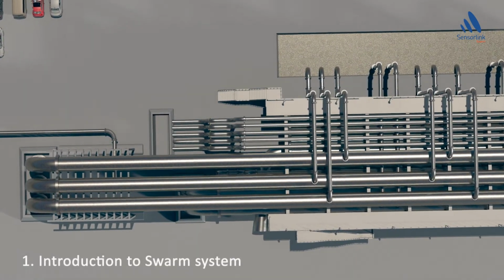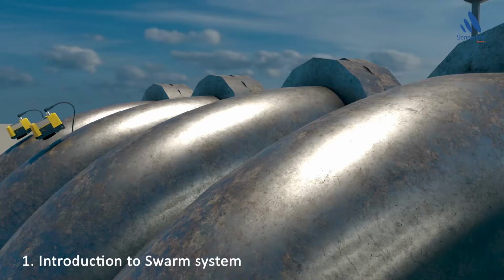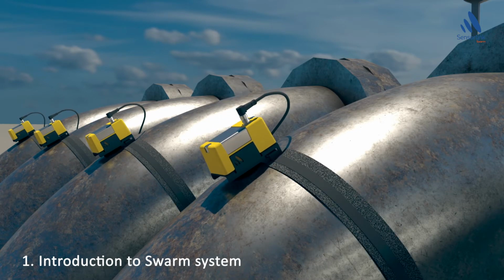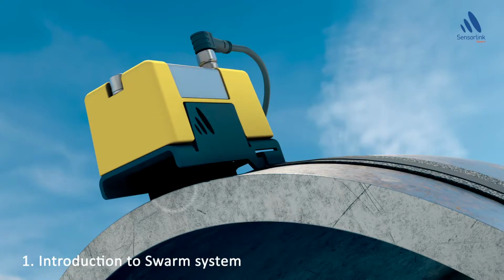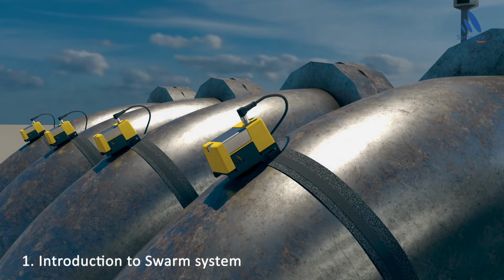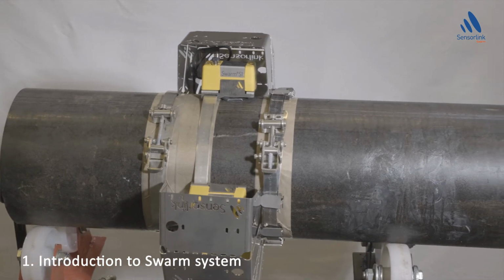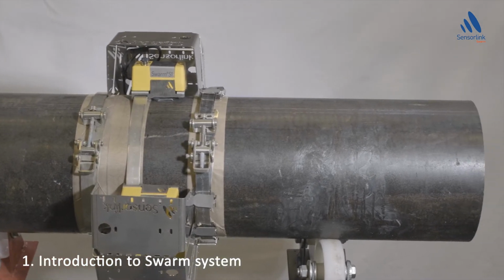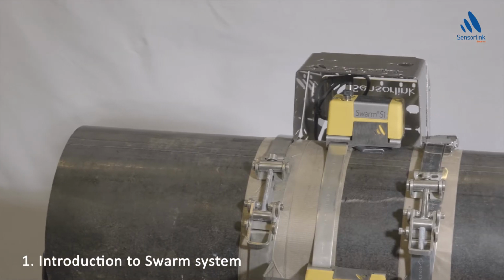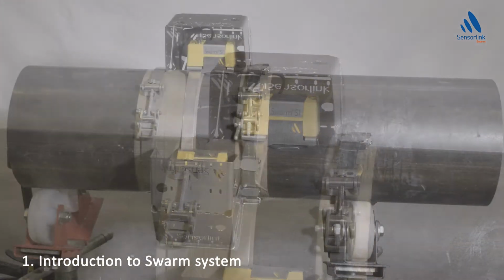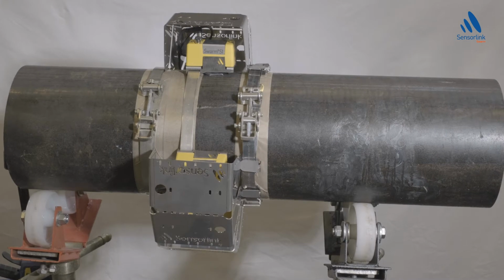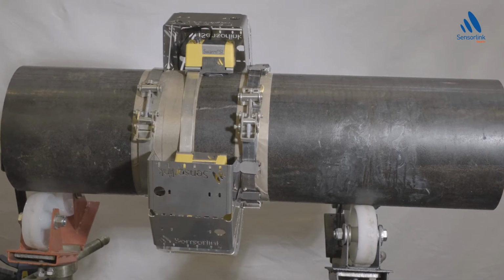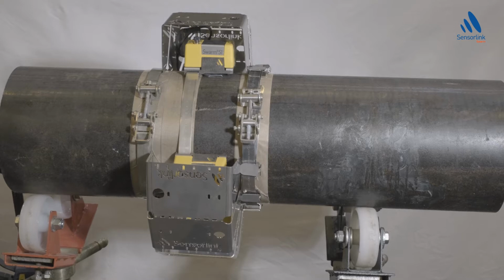This video is a brief instruction on how to install the Pipe Monit Swarm S1 sensors to the pipe. The Pipe Monit Swarm system is a high-resolution erosion and corrosion monitoring tool based on ultrasound that provides quick response to wall thickness changes in pipelines and vessels. It is non-invasive, installed and operated without interfering with production, and is certified according to ATEX and IEC-EX for Europe and International, and CSA for Canada and US.